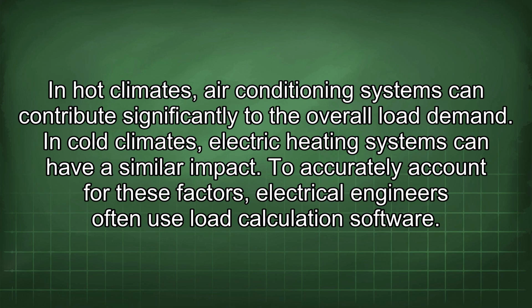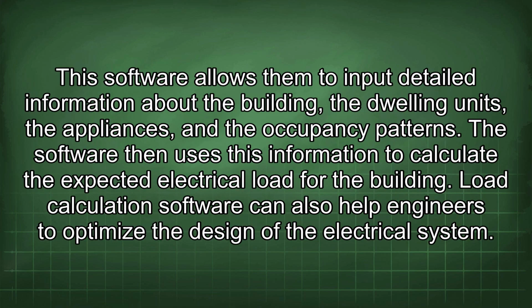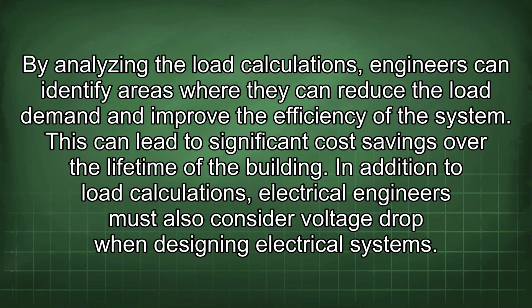To accurately account for these factors, electrical engineers often use load calculation software. This software allows them to input detailed information about the building, the dwelling units, the appliances, and the occupancy patterns. The software then uses this information to calculate the expected electrical load for the building. Load calculation software can also help engineers to optimize the design of the electrical system. By analyzing the load calculations, engineers can identify areas where they can reduce the load demand and improve the efficiency of the system. This can lead to significant cost savings over the lifetime of the building.